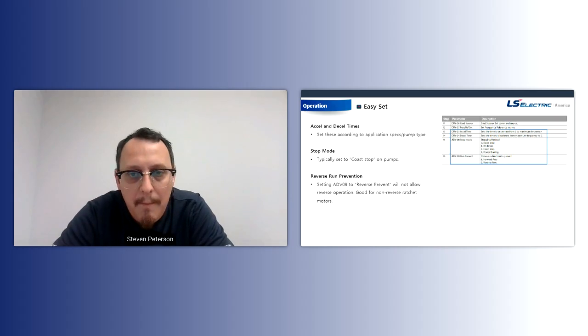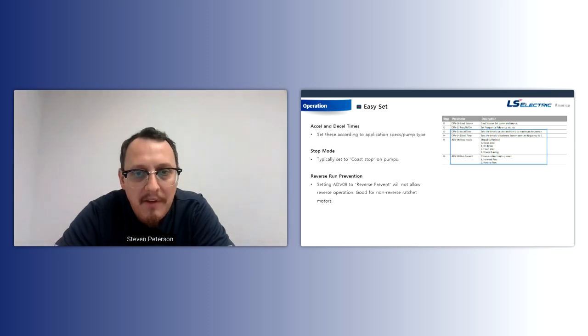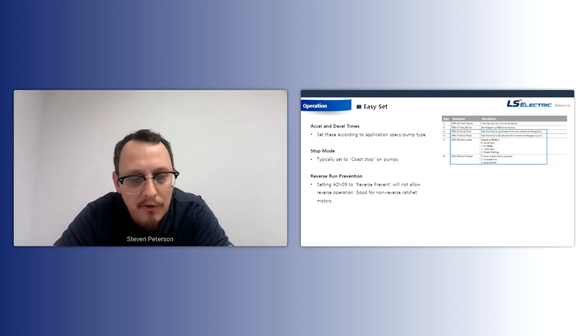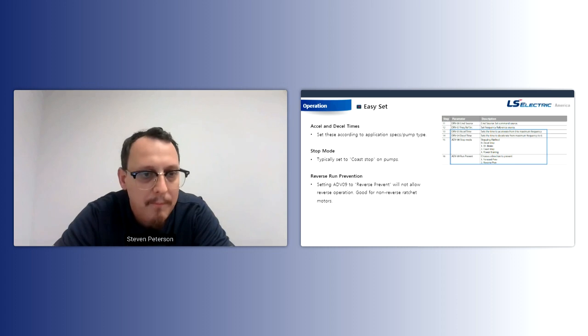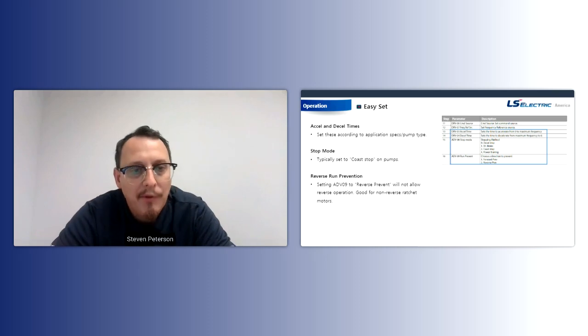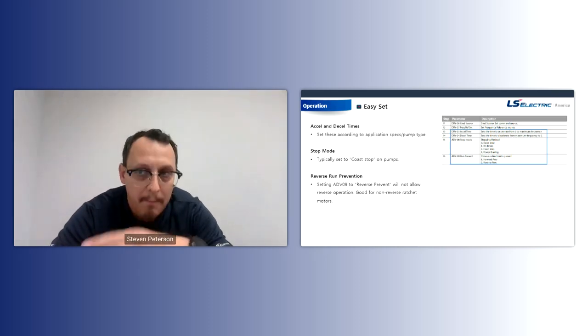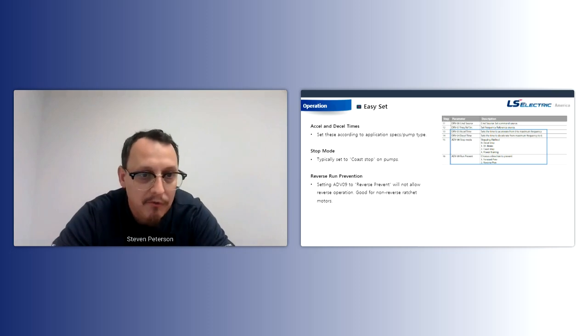Next up is the stop mode. So by default, if you don't use any macros, you'll see this goes to decelerate to a stop. So what that means is from 60 hertz to 0 hertz, while you're ramping down from your maximum to your minimum, it's going to follow a pre-programmed time of 20 or 30 seconds, for example, which you could always adjust. But a lot of pumps, we don't really care how fast it stops. So we just set it to coast to stop. Most of the guys that I talk to are perfectly fine with that. So they'd actually go here and set it to coast to stop. And what that's going to do is shut off the output, and then the pump just stops on its own, based on inertia and friction.